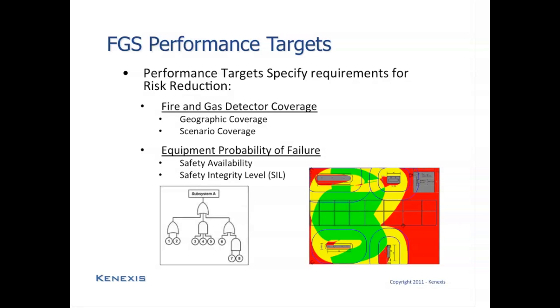Most of the order of magnitude or semi-quantitative techniques for fire and gas system performance design utilize geographic coverage techniques. So for most project applications, the coverage is going to be specified in terms of geographic coverage, and geographic coverage techniques will be used for coverage calculation for verification purposes. The other type of detector coverage is scenario coverage.